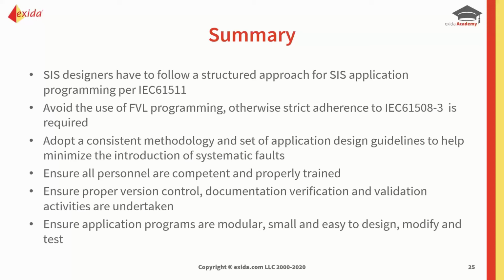And the last thing we want is bugs in the application program that can cause us to have either a failure on demand or could cause a spurious trip. We want to avoid the use of full variability programming. Otherwise, we have to have strict adherence to the 1508 requirements. So again, I can't emphasize that enough.